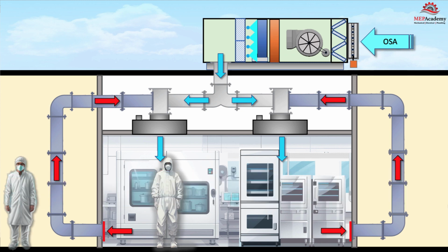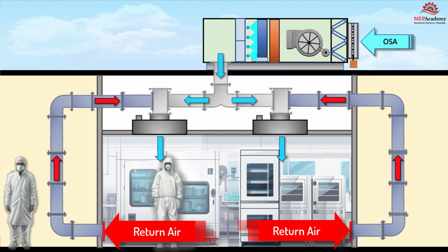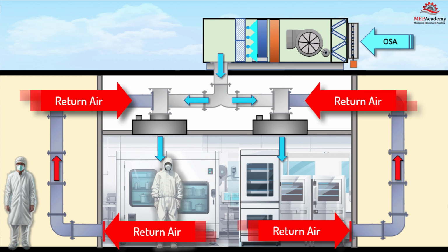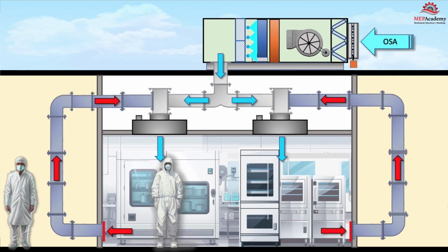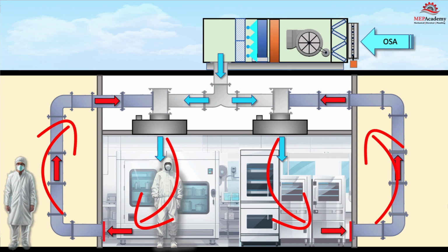Air handling unit and fan filter unit system number 2. With the second configuration, the air handler feeds the fan filter units as in system number 1, but the return air goes directly to the fan filter unit instead of the air handler. The air handler provides the required conditioning and outside air, while the fan filter units provide the required air changes to achieve the cleanliness level for the specified space.